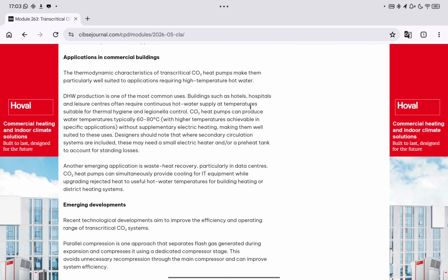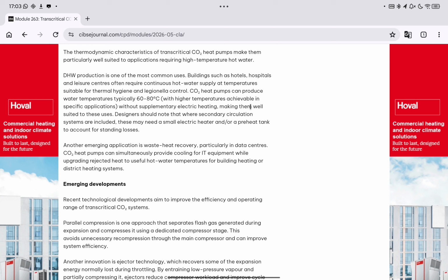Another emerging application is waste-heat recovery, particularly in data centers. CO₂ heat pumps can simultaneously provide cooling for IT equipment while upgrading rejected heat to useful hot water temperatures for building heating or district heating systems.